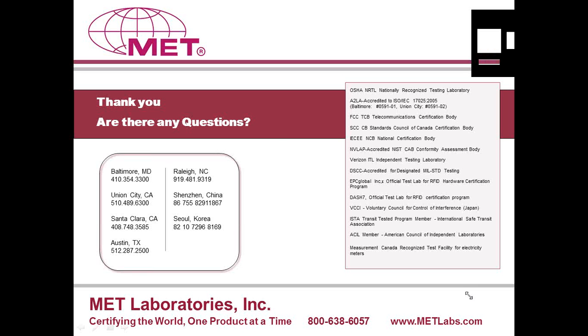Yeah, so we have a question that came in just now. What is the C12.16 standard? C12.16 is an older standard, and we do hear that requested occasionally. Really, what that is is an older version of C12.1 with all the criteria there. So that standard is no longer in force. Essentially, if you have somebody requesting C12.16, what you need to prove out is that you've tested to C12.1. It's the same set of criteria, really. It's, as I said, an older standard that's no longer in force. It's C12.1 that would really take the place of that.